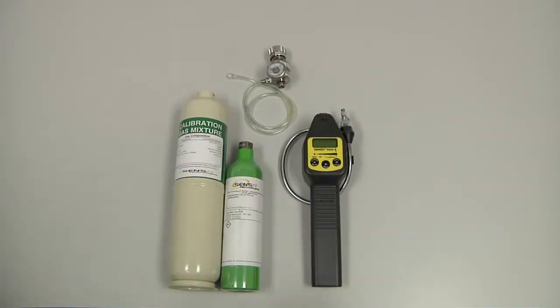To perform a manual calibration of the Sensit HXG-3P, we will need the instrument itself, a regulator with cal adapter, and the calibration gas, which is 50% LEL methane, or 2.5% by volume, or alternatively 50% LEL pentane, or 0.75% by volume.